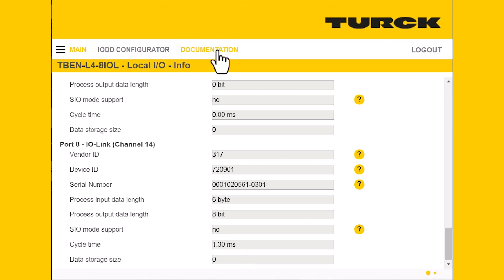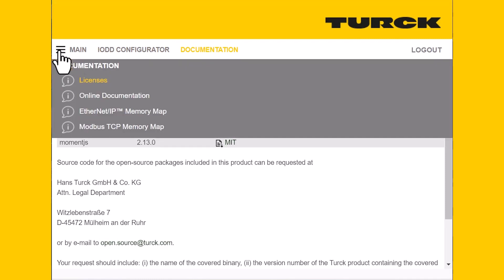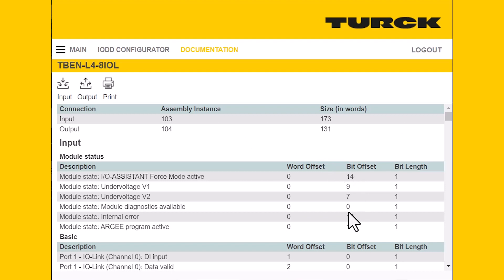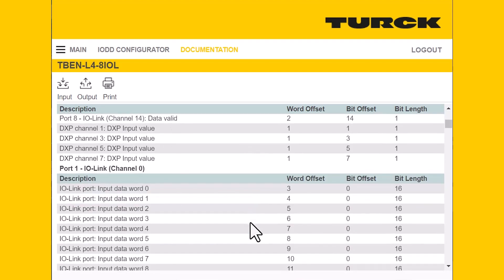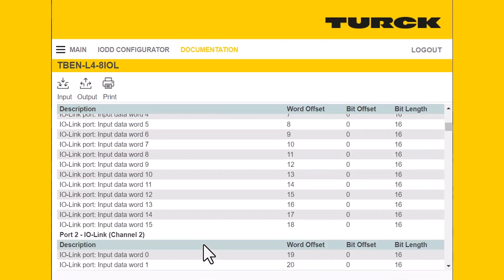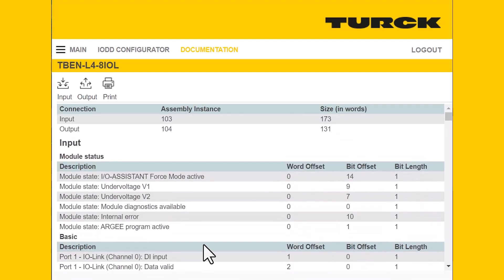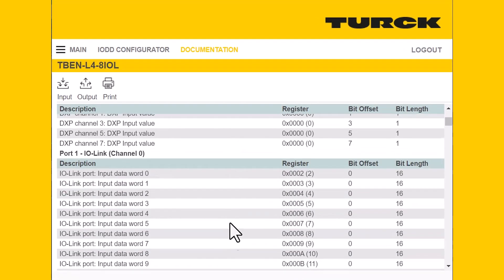Next, I'll hop over to documentation at the top. The primary two tabs that are most useful here are your EtherNet/IP memory map and your Modbus TCP memory map. These tell you exactly where you can find specific data from the device — for example, port 1, IO-Link channel 0, giving you a word offset, bit offset, and bit length. This is extremely useful when you're trying to configure this in a PLC. We also have the Modbus TCP data map as well.